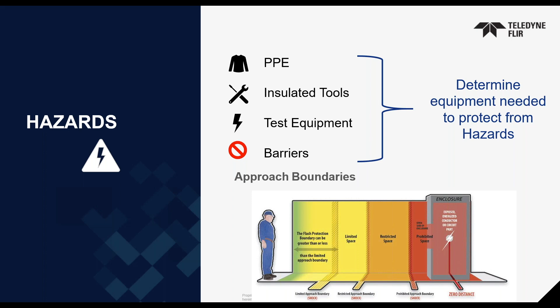On the bottom of the screen we have the approach boundaries, from limited approach down to zero distance. These are all clearly defined in 70E based on the type of PPE, as well as any necessary barriers or equipment you'd want to use when performing testing or inspections.